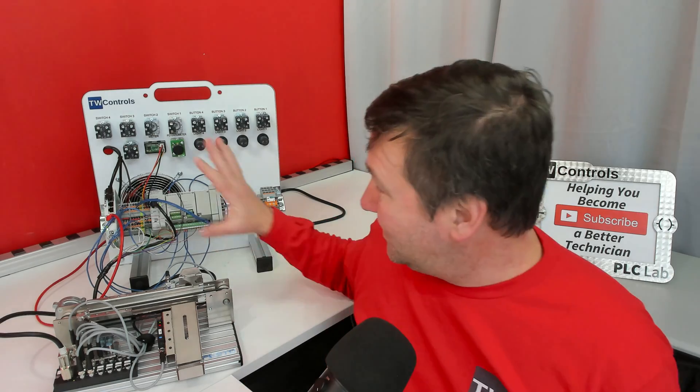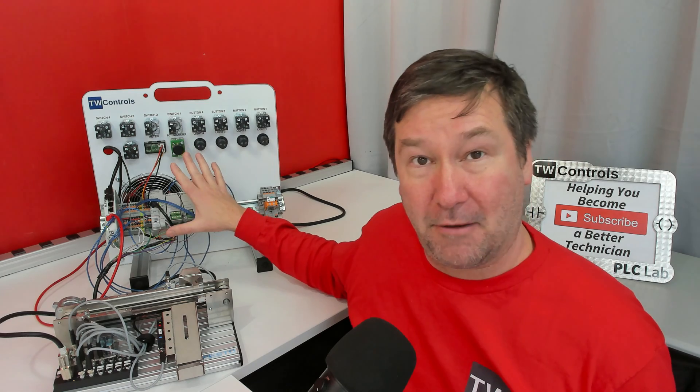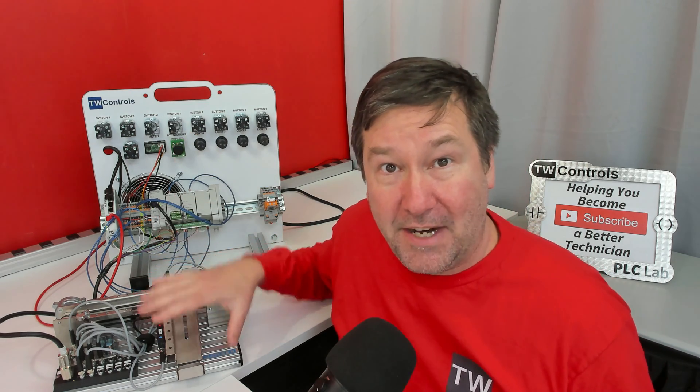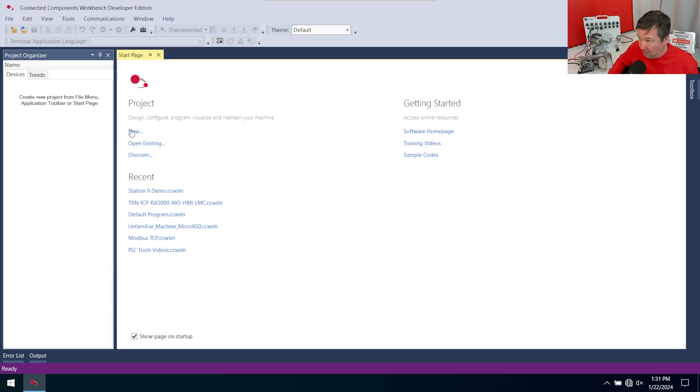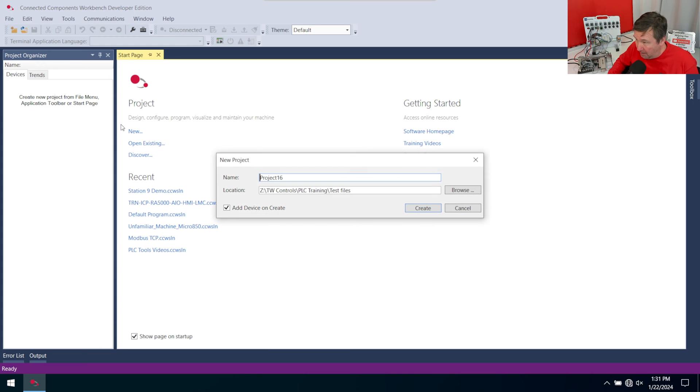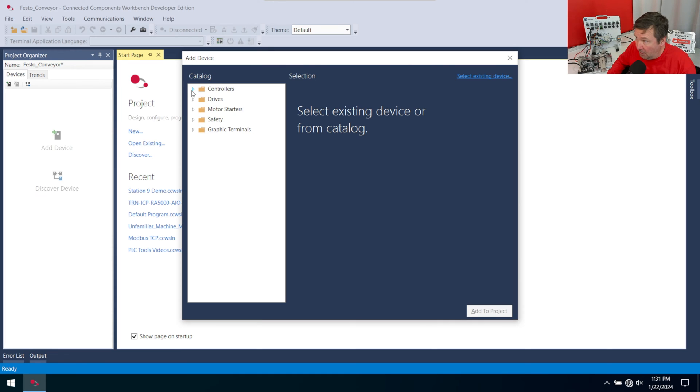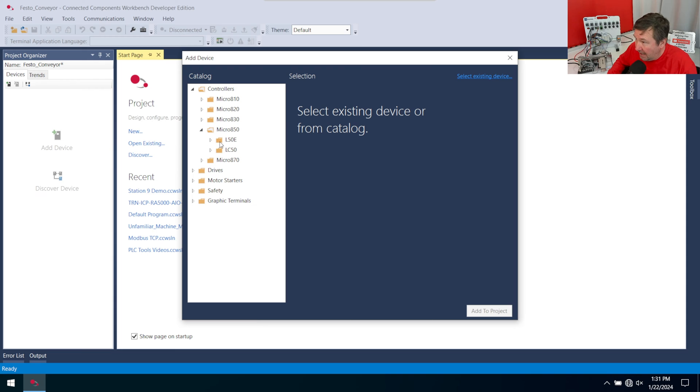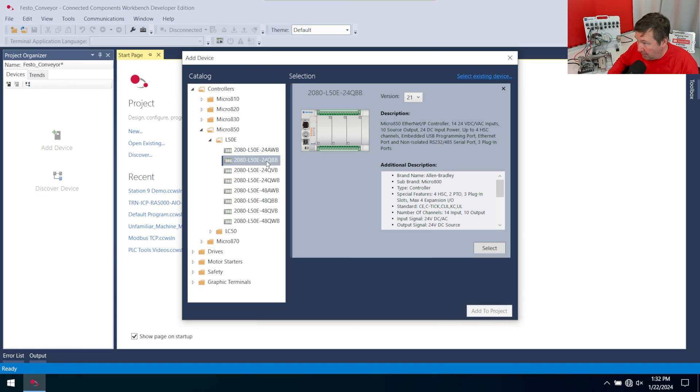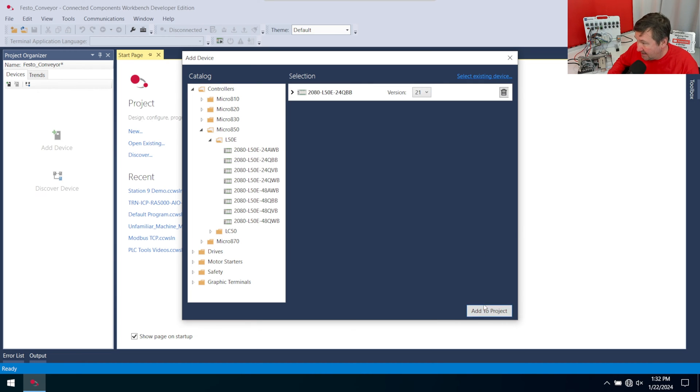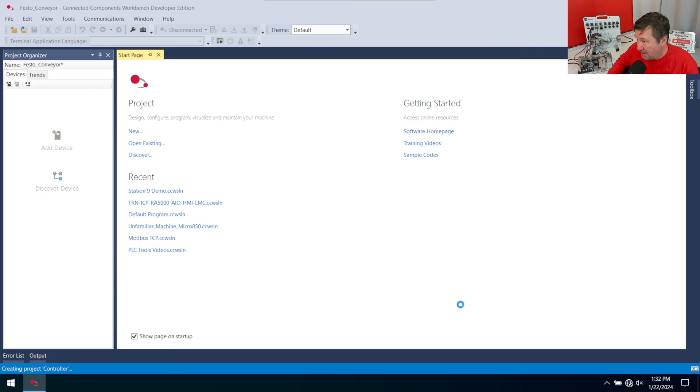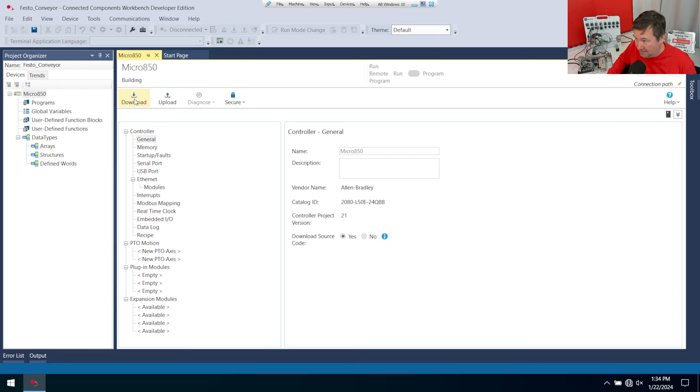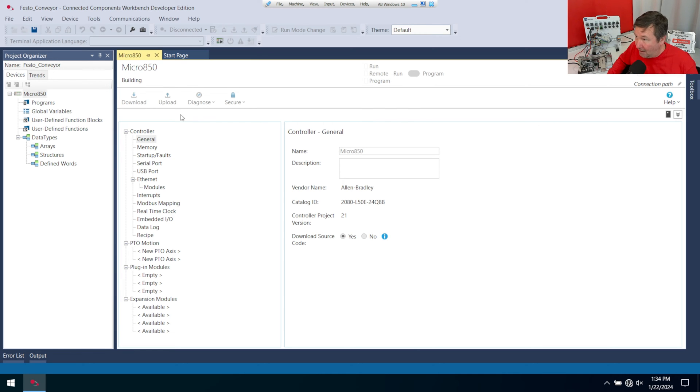Before we go any further, let's test the integration between our PLC trainer and the Festo didactic conveyor. And we're going to start with a new program in Connected Components Workbench. And I'm going to call this my Festo conveyor. Then go into controllers, micro 850. And in my case, I'm going to go into the L50E. And I have a 2080 L50E 24 QBB. We're going to hit select, add to project, add to project. And you're going to think I'm crazy at this point. But we're going to go and download this blank program here. Because we can use this to test our IO before we start doing any programming work.